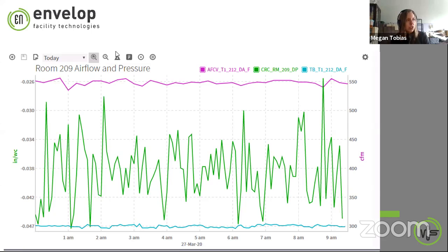What's interesting is these rooms weren't initially designed to be isolation rooms, so they don't have the two VAV boxes serving the space, just the one. So what they're actually doing is installing exhaust fans in the windows to expel enough air from the space versus what's being supplied, to make sure the room goes into a negative pressure situation.